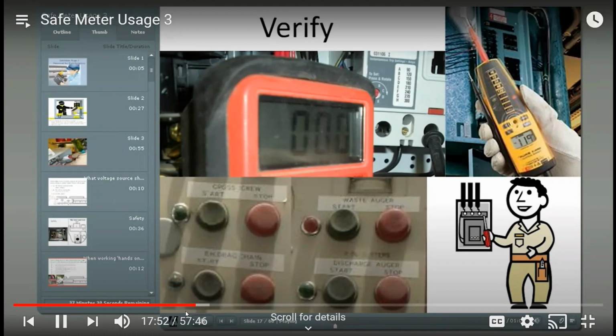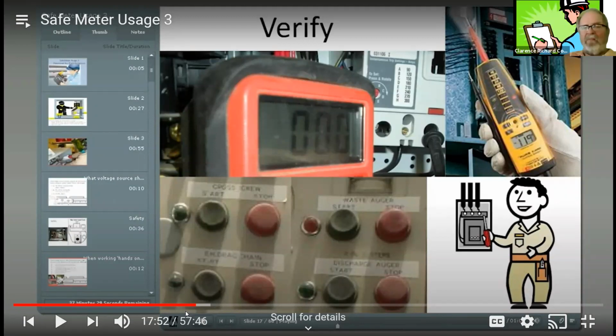I want to ask a question, and I really don't know for sure. Okay, let's hear you. Can you hear me? Yes, we can. Anything I've done at a plant, I've never had to use anything but ohms or voltage, but why would you ever be checking ohms with any power on at the plant if you're just checking resistance? Voltage, I could see checking with power on, but why would you ever check ohms with power on? You would not. It gives you a bad reading and it hurts the meter and it might hurt you.